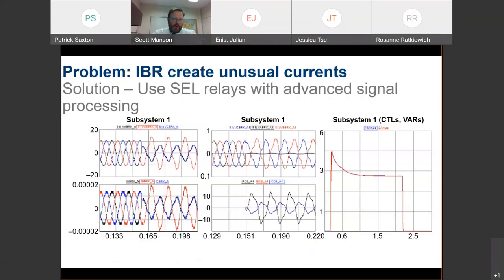Now, inverter-based resources, I'll call them IBRs henceforth. IBR is a common acronym. These IBRs create unusual currents, currents being the flow of electrons in the AC, and they create currents that we didn't see before. Generators can't produce this kind of current. It's anomalous current. It's current that comes from firmware, rather than the physics of an electromagnetic interface between a rotor and a stator in a synchronous machine.